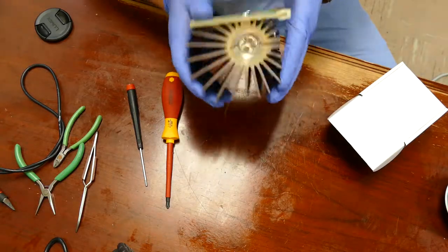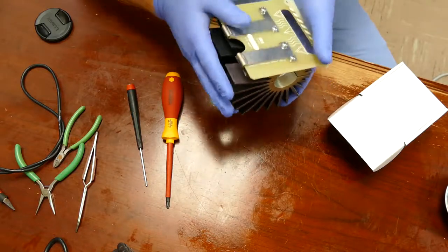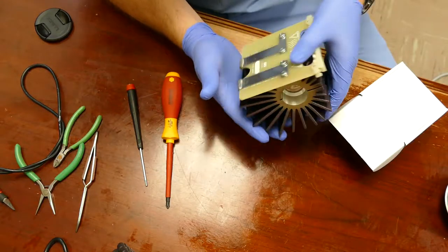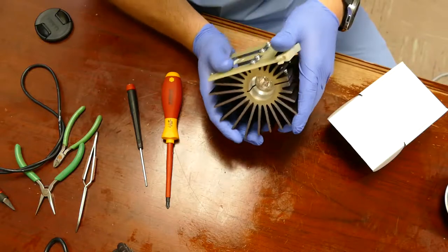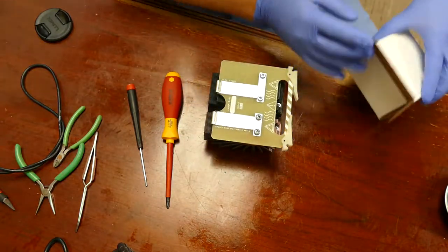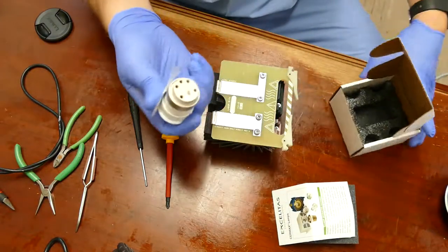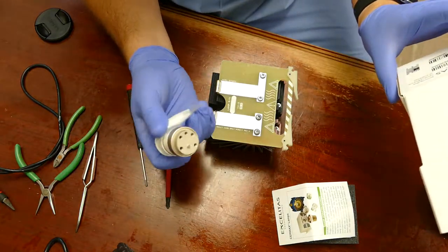Here you can see the bulb holder. Some hospitals tend to just ship these out to Karl Storz and buy whole replacement ones, and that's very expensive. That can be well over $1,000 if I remember right, versus just going out and buying the bulb, which you can see here. I believe it's $220 to $250.